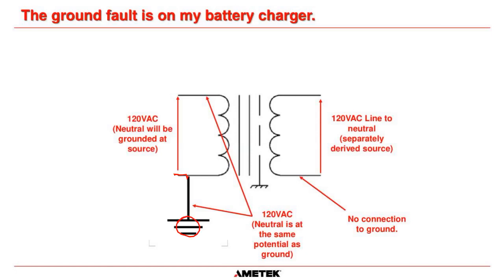Okay. Now, we don't even run the neutral to our chargers. We don't need a neutral for our system. So we don't even look at the ground connection here. But the important thing is there is isolation between the primary and the secondary of the transformer. Okay. So therefore, we're creating a separately derived source. And if we do not connect it to ground at this point here, then it has no reference to ground. Okay?